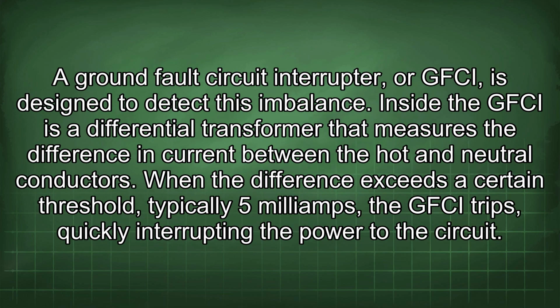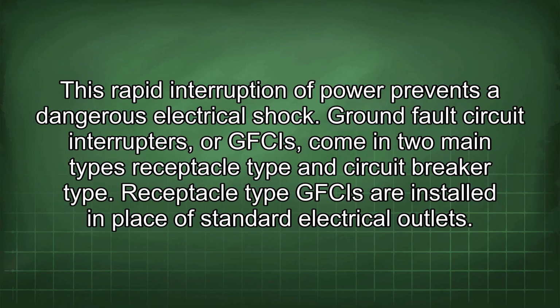A ground fault circuit interrupter, or GFCI, is designed to detect this imbalance. Inside the GFCI is a differential transformer that measures the difference in current between the hot and neutral conductors. When the difference exceeds a certain threshold, typically 5 milliamps, the GFCI trips, quickly interrupting the power to the circuit. This rapid interruption of power prevents a dangerous electrical shock.